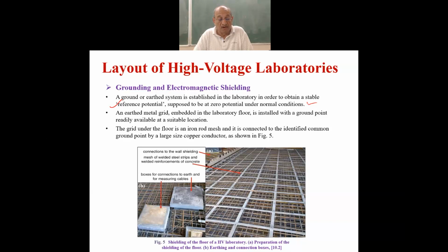You can imagine that. So all high voltage laboratories are provided, on their floor below the finish, an iron grid which is grounded at specific locations. An earth metal grid, as you can see, is embedded in the laboratory floor, with ground points readily available at suitable locations. So this is a provision. The grid under the floor is an iron rod mesh, and it is connected to the identified common ground point by large size copper conductors, as shown. So the grounding of the floor or of the laboratory is also very important for safety purposes. So these are the aspects which are important when you set up a lab.